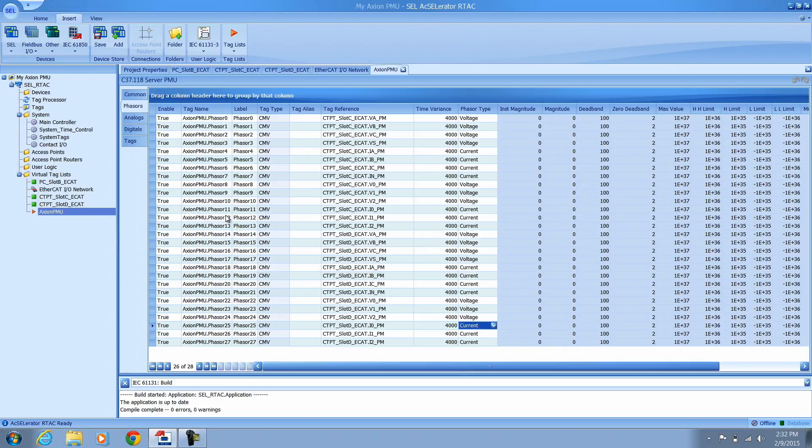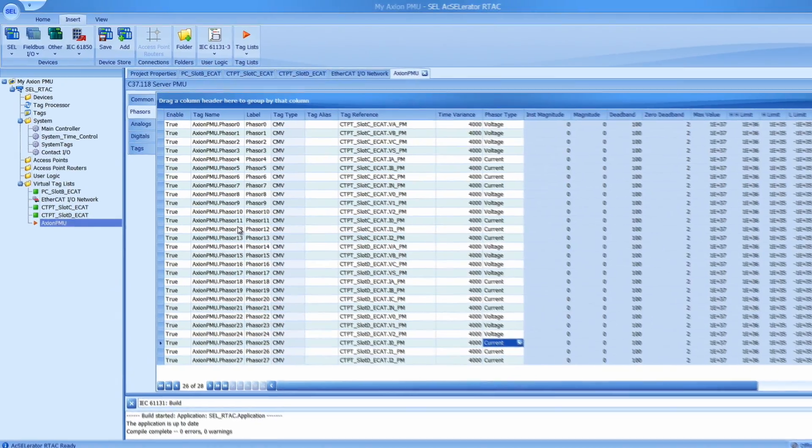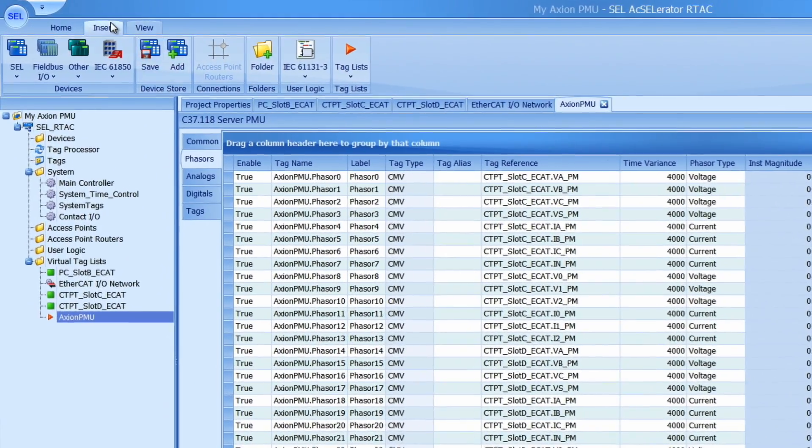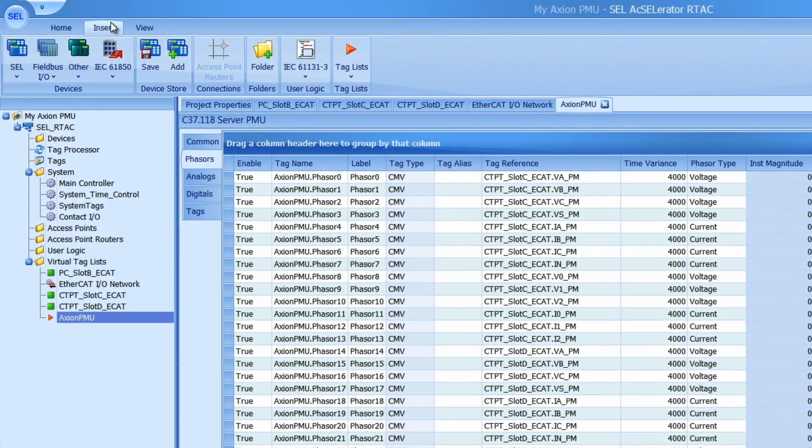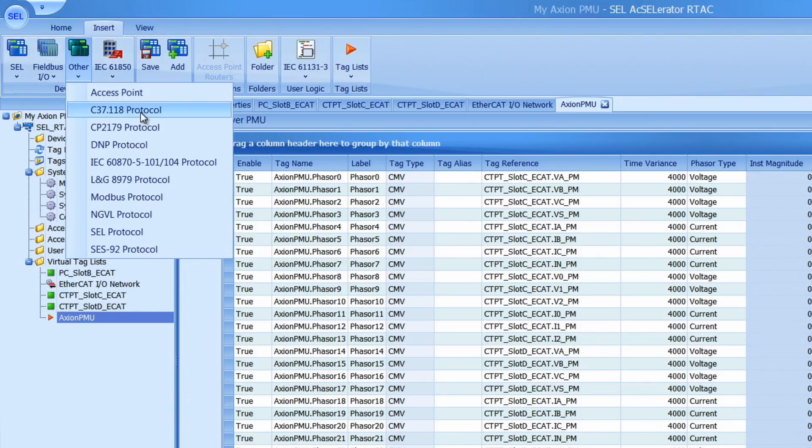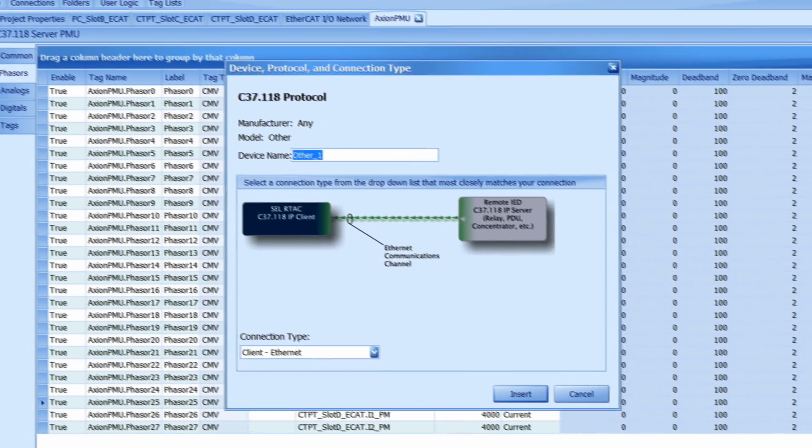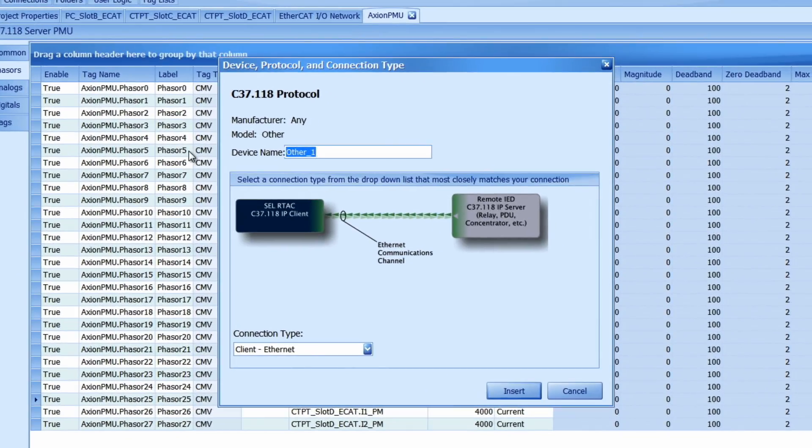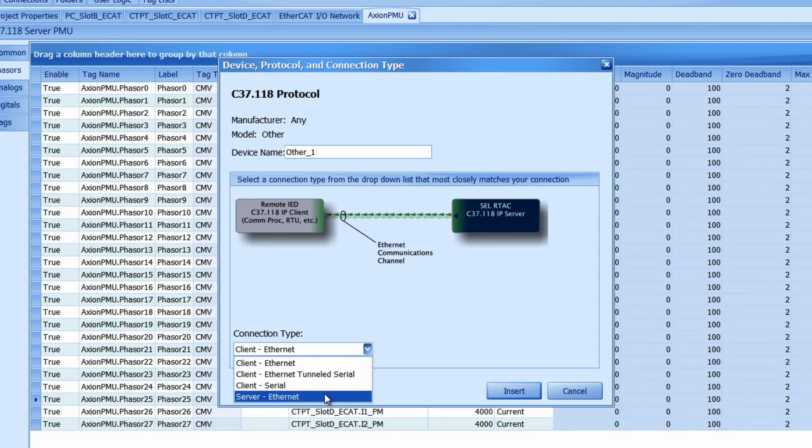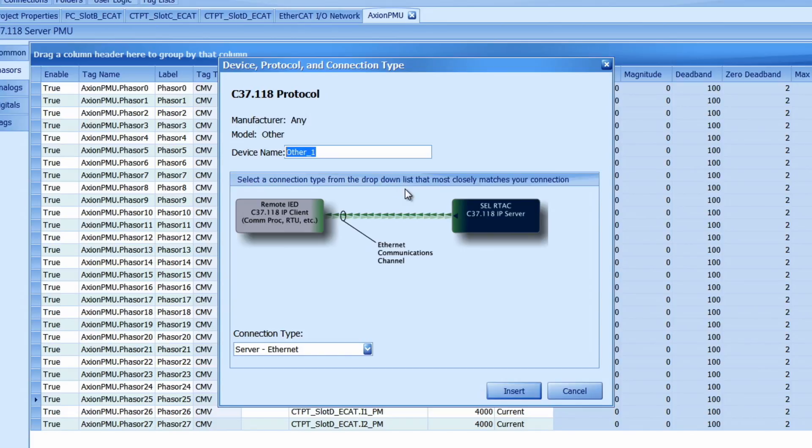So the last thing we have to do is create our C37.118 server and map our virtual tag list to it. Go once again to the insert tab. Go to other and select on the C37.118 protocol. When this window pops up select the server ethernet for the connection type and then name the server as you would like. I'm going to call it Axion PMU server and click insert.